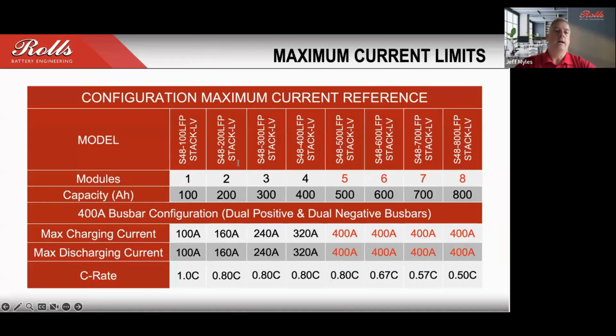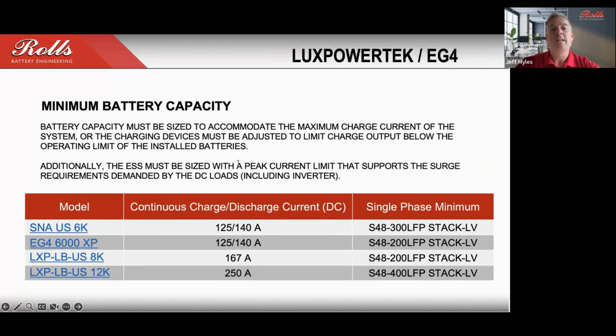One thing you also need to consider when you're setting these up with a particular inverter is the current limits for the stack, based on the number of batteries that you're connecting. I mentioned before that the bus bars are dual bus bar, allowing up to 400 amps of charge and discharge current. But we also need to look at the current limit of the batteries based on the BMS. In the installation guide, at the beginning of each section, depending on which inverter you're connecting with, we've outlined the minimum number of batteries for that particular stack. In this case, for the SNA 6K inverter, the minimum would be 3 units.